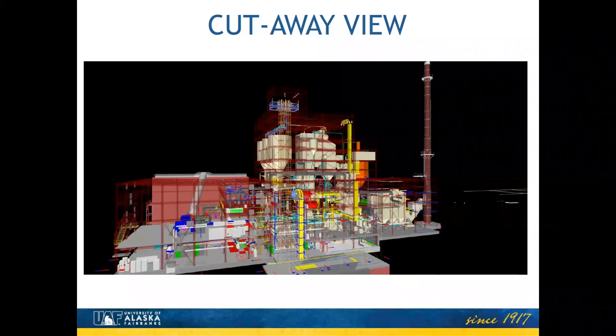Then the center portion of the building, in the foreground, that's the material handling and coal offloading area. And there's rail tracks that run through that, following the same path that the previous ones did. And coal is delivered by rail car and offloaded there. From there, it's conveyed up to a crusher where it's sized to the gradation that the boiler wants to operate efficiently. And then from there, it's delivered up to storage silos up towards the top of the building. Then in the background of that center section is the boiler itself. On the left-hand side, you can see the coal storage silos. There's three of those that all feed the boiler simultaneously. And when the boiler runs at maximum rate, there's 3 days worth of coal storage in those.